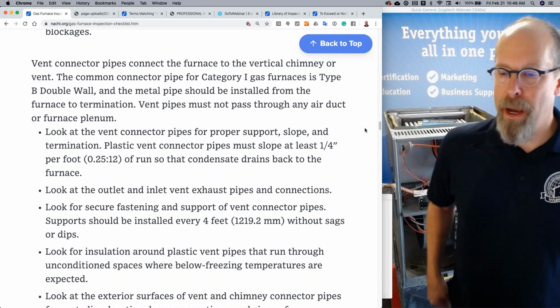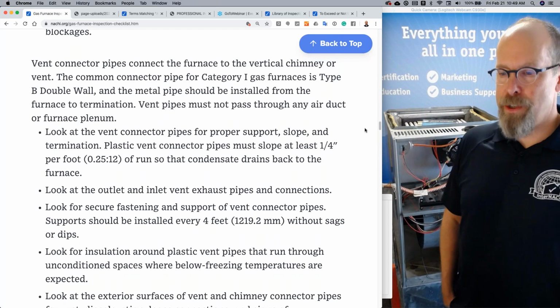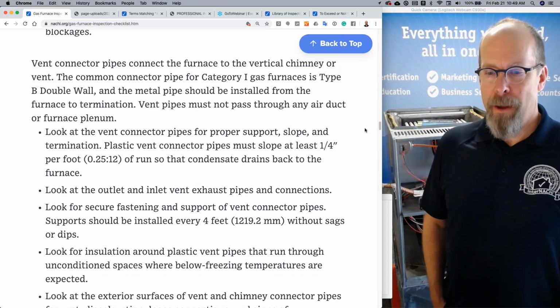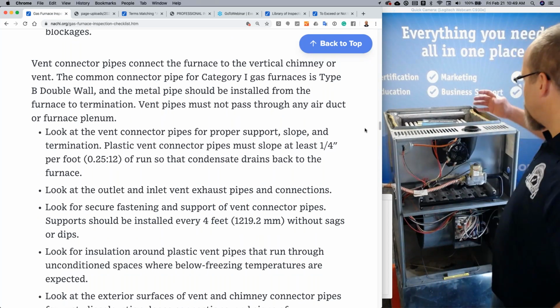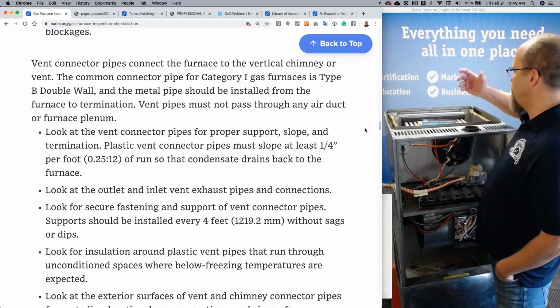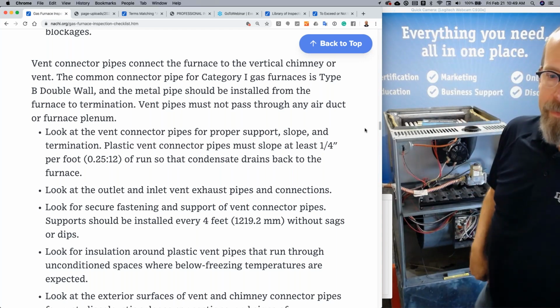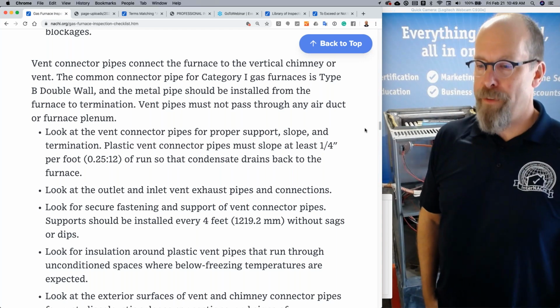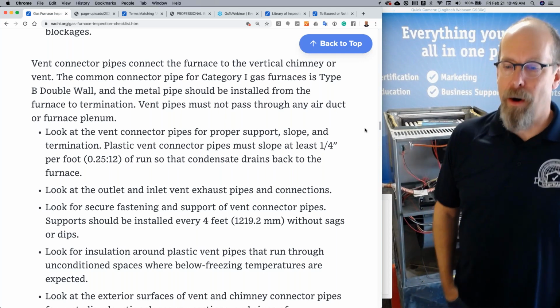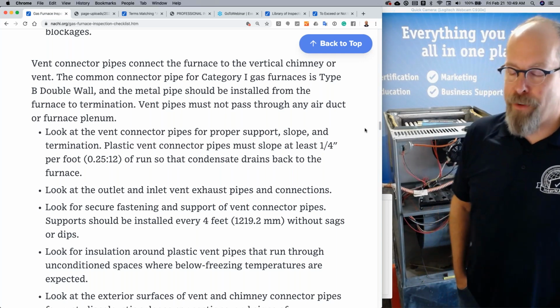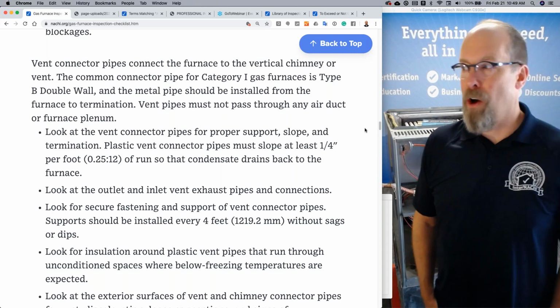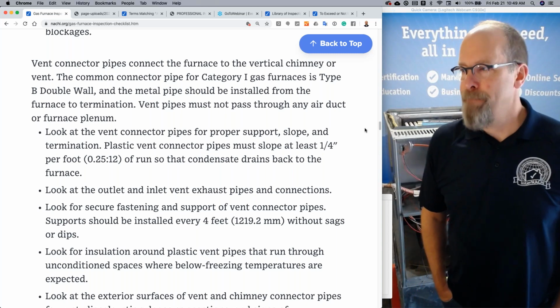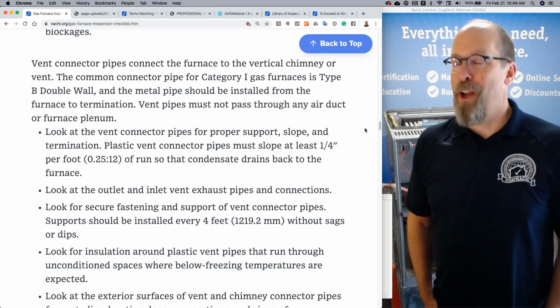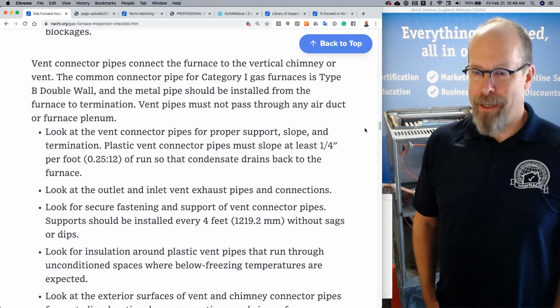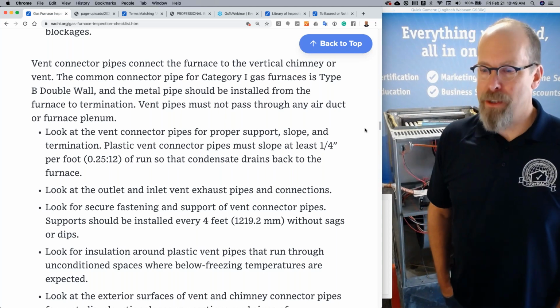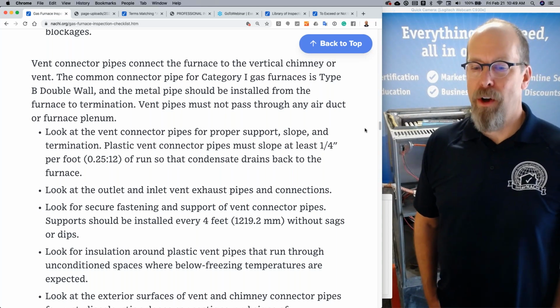Vent connector pipes connect the furnace to the vertical chimney or vent. So that's the vent connector pipe. This metal pipe, we call it the vent connector pipe. The common connector pipe for category 1 furnaces is type B double wall, and the metal pipe should be installed from the furnace to the termination. That's all metal. There shouldn't be any different kinds of material. No wood, no plastic. And vent pipes must not pass through any duct or furnace plenum.